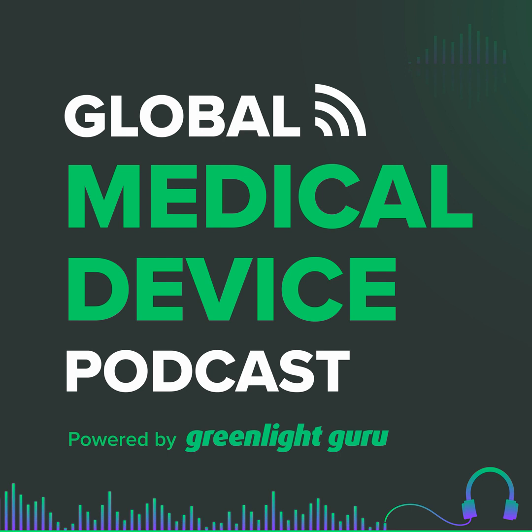I highly recommend, if you haven't taken the opportunity, to go into the FDA's database, type in your product code, go to that product code's product lifecycle report, and look at all of the harms, and it even has hazards in there, of the issues that have happened with the devices in that same product code. Take a look at that. It has such valuable information, and you can do that from the very beginning of your design. Before you even develop the first thing about your product, when you just have an idea of what you want it to be, you can go look that up and you can start your design with all of that risk in mind. But I deviated like 6 different times when I was talking.